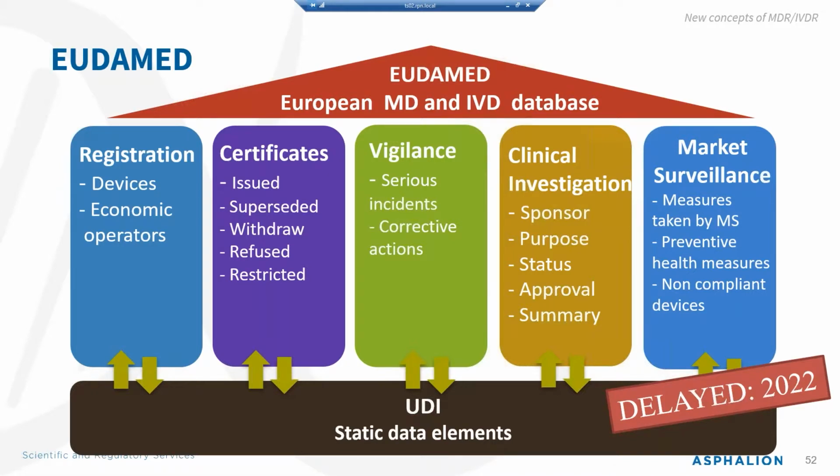Okay, in EUDAMED you will see the measures taken by the member states, preventive health measures and actions, and which devices have been defined as non-compliant with the regulation. Everything should be seen here in EUDAMED. This was described in the regulation when it was released in 2017, but it has been delayed to 2022. It's not going to be active until 2022. Okay. This is going to be very, very linked to UDI.